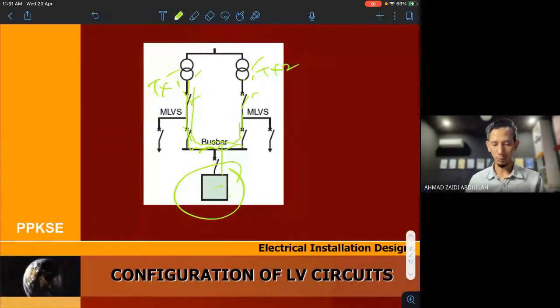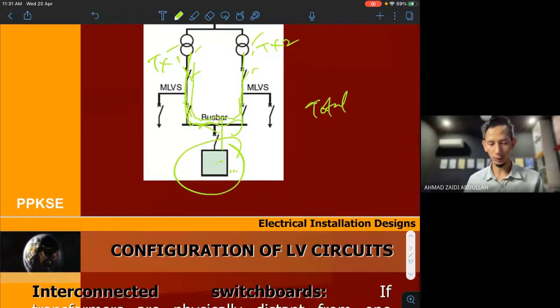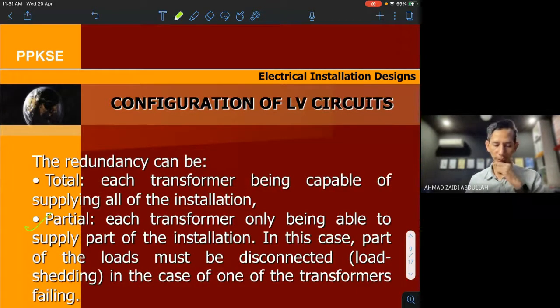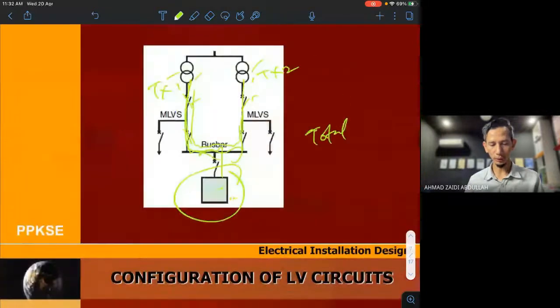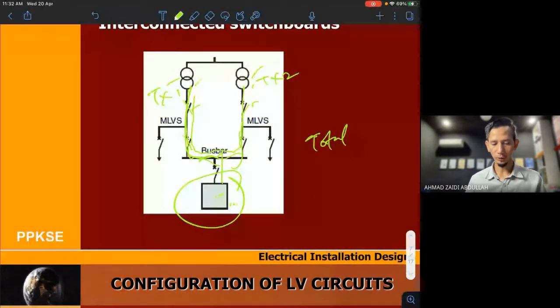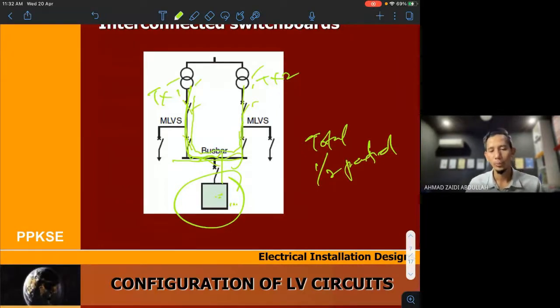This supply, when you talk about total, it means that it can get supply from this one and this one at the same time for the whole. And then partial means that each transformer is only able to supply part of the installation. Part of the load must be disconnected. So this, for example. So this load of this bus bar is only possible for half, partial. So, a portion.